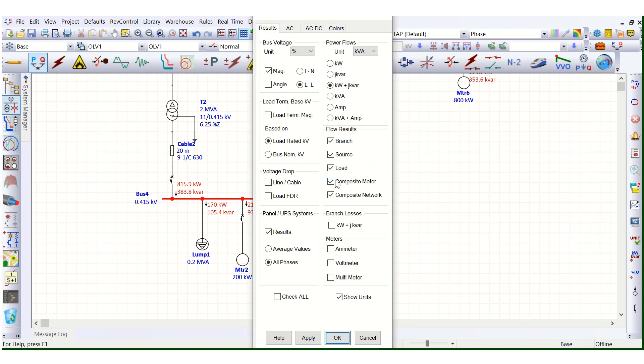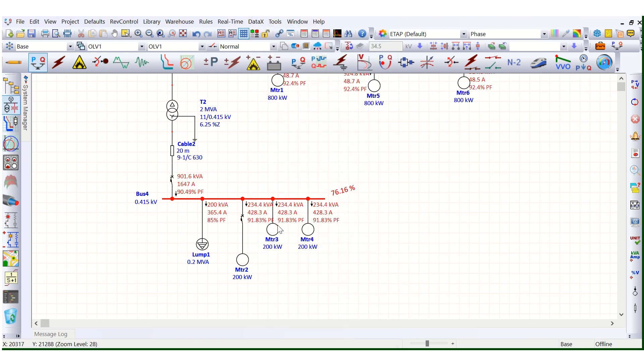Let's check the kVA and power factor as well. Here the power factor is 90.49%, and for this load, 85% for the motor — 91.83% power factor. That's fine, but to sort out the bus voltage issue, the voltage drop means you need to realign the connected loads.